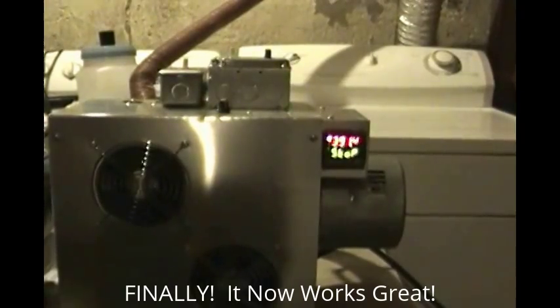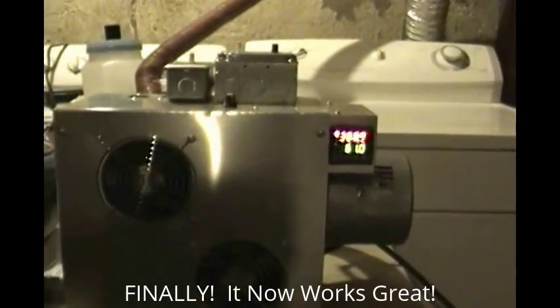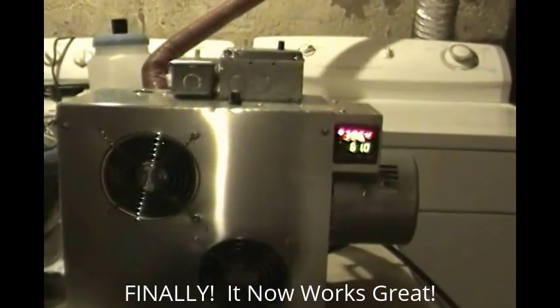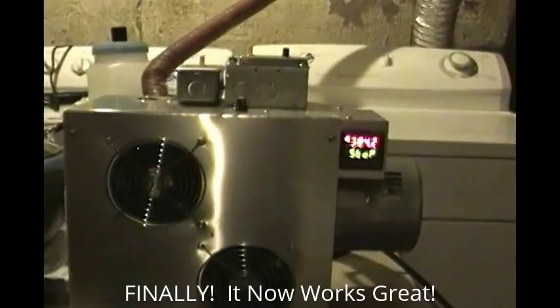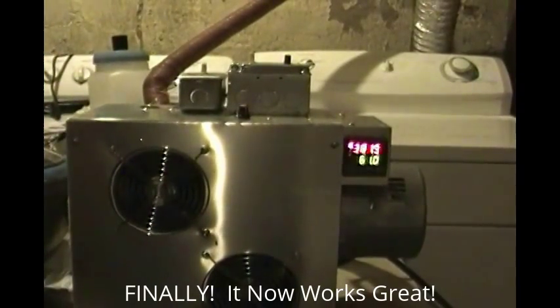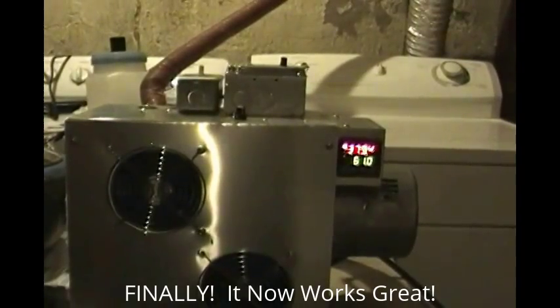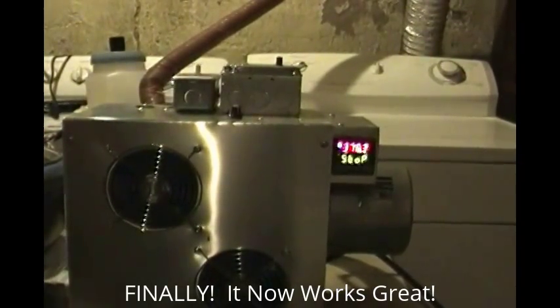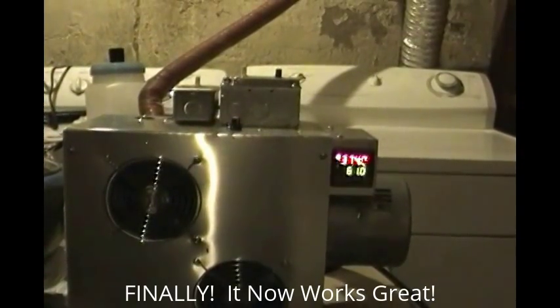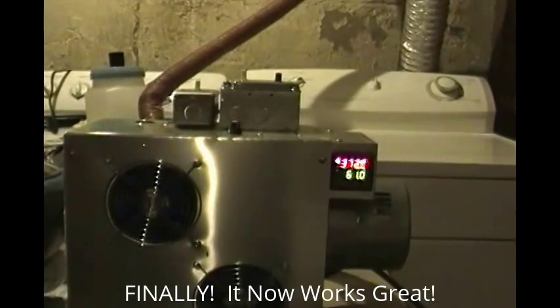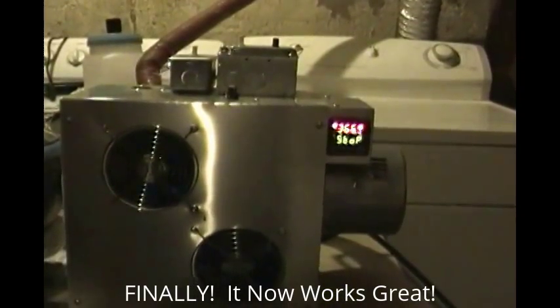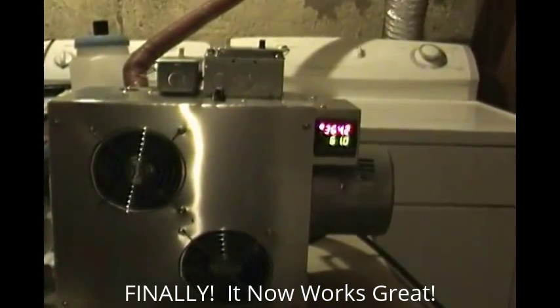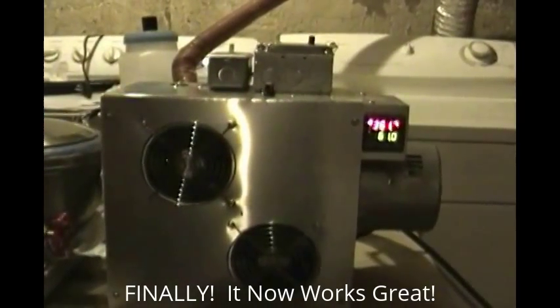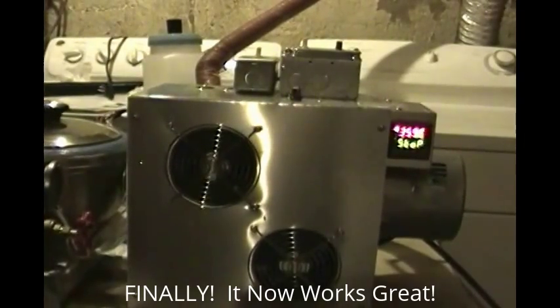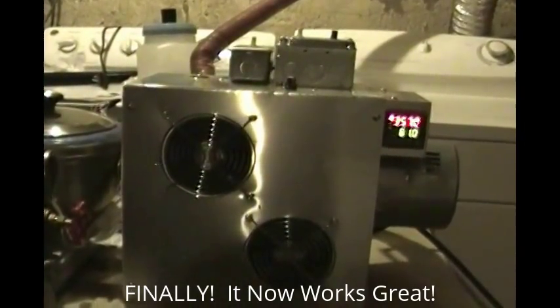Not your typical variable rate AC device, it's actually a DC device. It varies the DC voltage from 0 to 9 volts DC, feeding that voltage signal into the electronics of the vacuum motor. The vacuum motor itself has electronics because it's used in the health industry for raising and lowering and working with hospital beds.